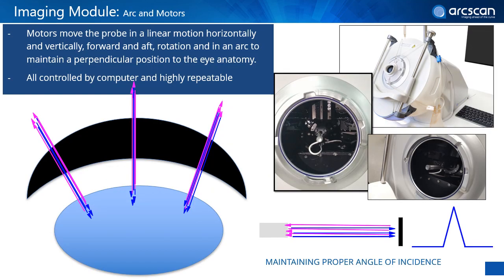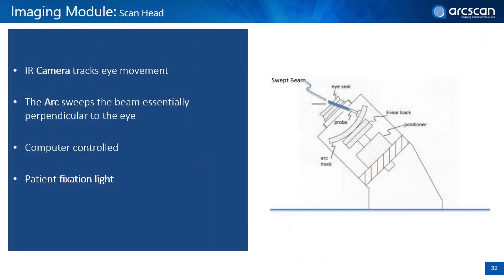The motors inside the device move the probe to maintain that best angle of incidence and the best beam focus, horizontally and vertically on the XY axis, toward and away from the eye on the Z axis, rotational, and the most important part of the Insight is the arc motion parallel to the eye with a perpendicular probe position, all controlled by computer. Also inside of the scan head is a camera so the operator can view the patient's eye while scanning, as well as a fixation light for the patient.